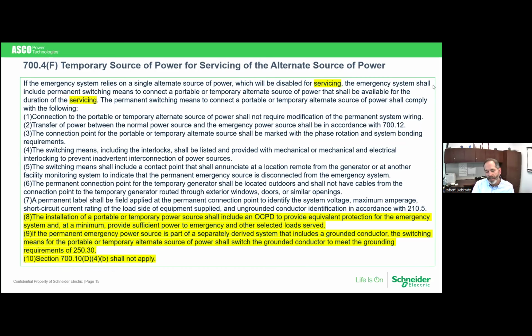So what they're stating here is that if you have a single source of power, you will have an easy way to hook up a temporary source of power. It'll be permanent. It's got some safeguards on it to make sure that it doesn't parallel with anything. It's got assurances that you're not going to be messing with any of the permanent wiring on the site. So I'm not going to read through each one of the 7 steps that have not changed in wording, but let's focus on the 3 that they actually added that are new. They're saying if you hook up a temporary generator, they want to make sure it has an overcurrent protection device in it to protect the downstream equipment and cabling. So they want a circuit breaker in there with that temporary generator. Understandable.